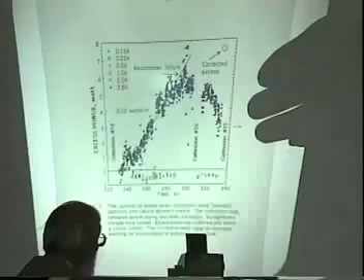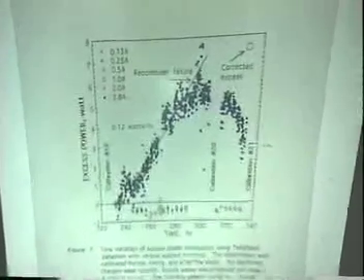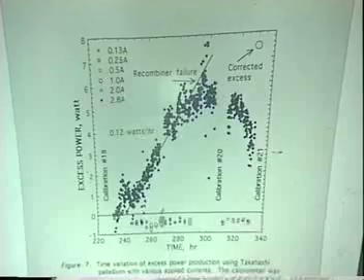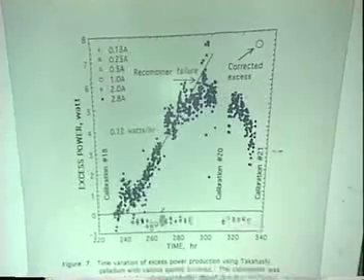So he sent me a sample of his material, and I put it in my calorimeter. And this is what we got. Now, I might point out this calorimeter can be calibrated on the fly. It contains an internal joule heater, so you can calibrate it as you go.